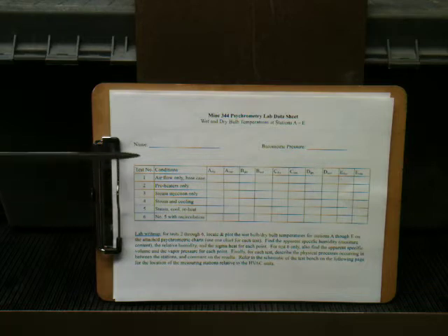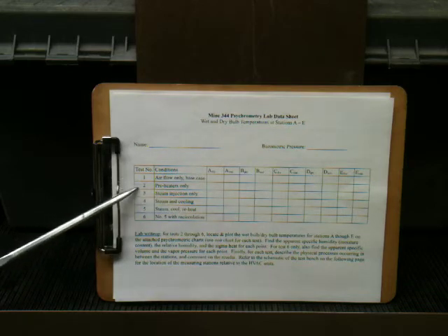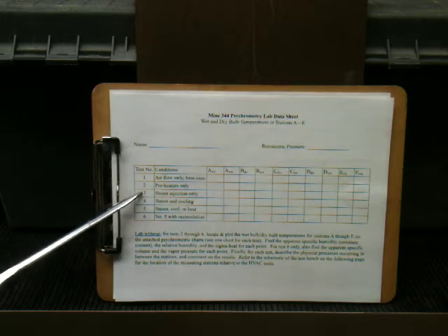On the data sheet, our first column on the left side is the test case number, 1 through 6. The second column indicates what the conditions are of each test. So we have the base case, that's just air flowing through the unit. We're not doing anything to it. Second case, test number 2, is the electric preheaters only. For test number 3, we turn off the preheaters and turn on the steam boiler, and we leave that on for the rest of the lab session.